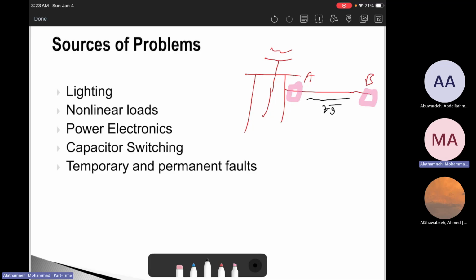So again, power quality problems are not bad engineering, but they are often side effects of good engineering done without full consideration. The people who designed the power electronics don't have a bad intention to impact the grid. They make good devices that can be very great, but there is a side impact, and you need to take the power quality issue into consideration.